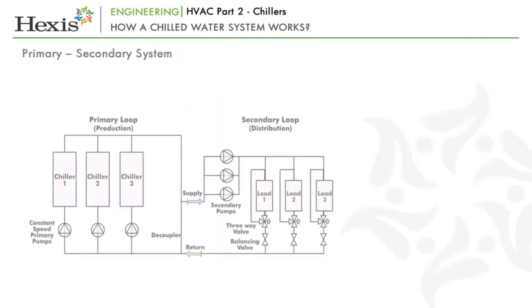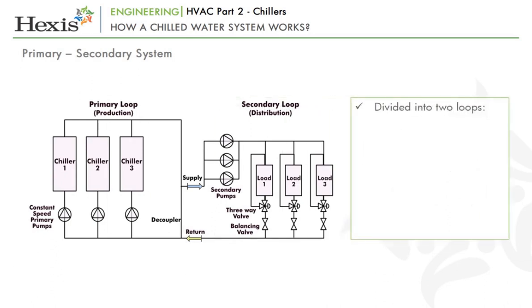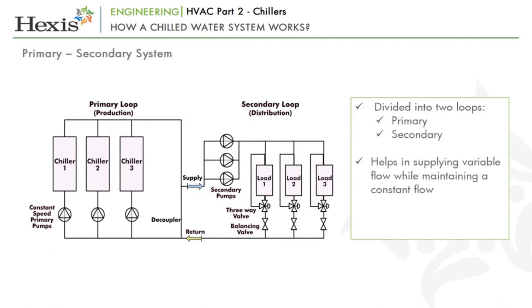In the primary-secondary chilled water system, the chilled water system is divided into two distinct loops: primary and secondary. This arrangement can supply variable flow through the system while maintaining a constant flow through the chillers. The secondary loop contains three-way valves to control the flow of water through the air handlers depending on load. However, the overall quantity of water through the system will remain the same.